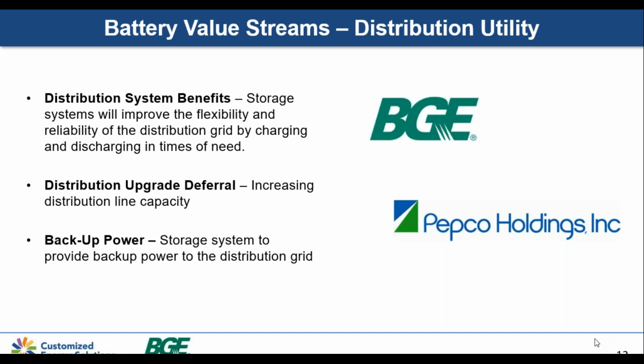Specifically, the utilities needed to have the battery available for certain times of need. This is either potentially during a peak time, but also looking at backup power. If they just have a unit trip offline or such, how can the battery help there? We considered certain hours that the utilities were going to use these batteries, and then we built that into the overall modeling of the system.